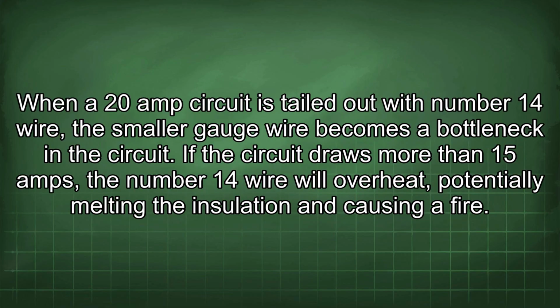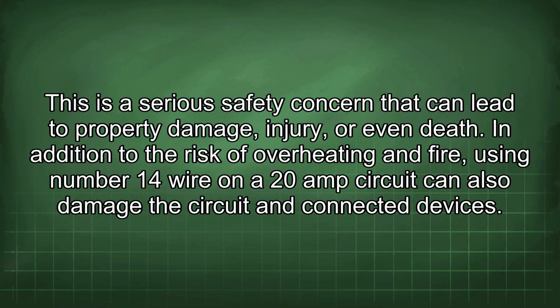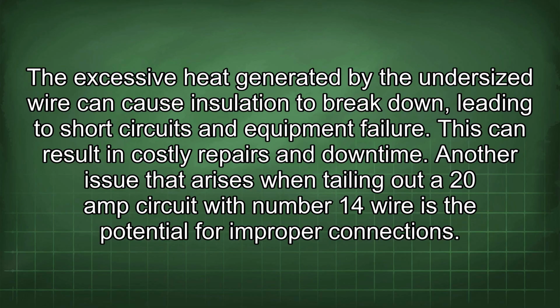When a 20 amp circuit is tailed out with number 14 wire, the smaller gauge wire becomes a bottleneck in the circuit. If the circuit draws more than 15 amps, the number 14 wire will overheat, potentially melting the insulation and causing a fire. This is a serious safety concern that can lead to property damage, injury, or even death. In addition to the risk of overheating and fire, using number 14 wire on a 20 amp circuit can also damage the circuit and connected devices. The excessive heat generated by the undersized wire can cause insulation to break down, leading to short circuits and equipment failure. This can result in costly repairs and downtime.